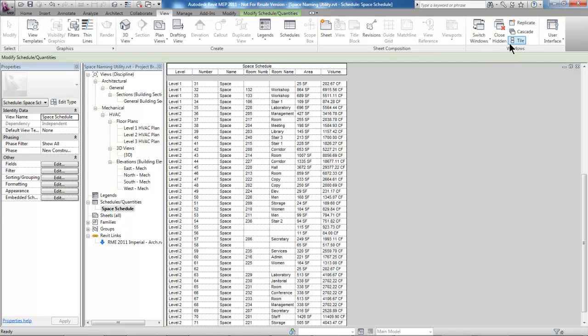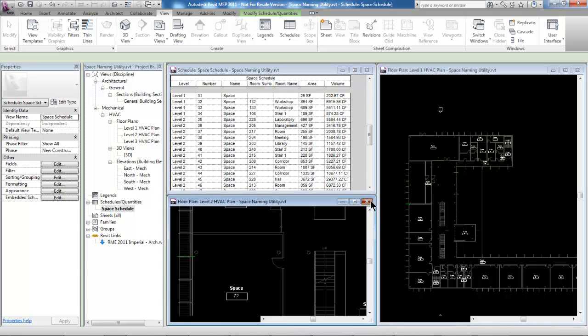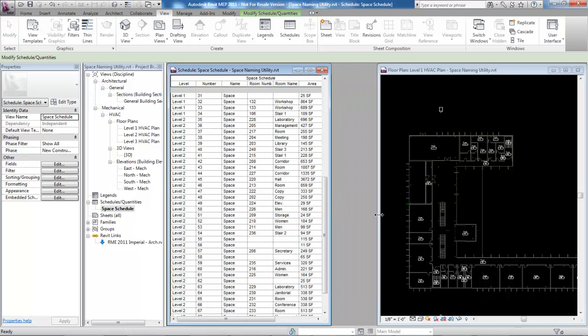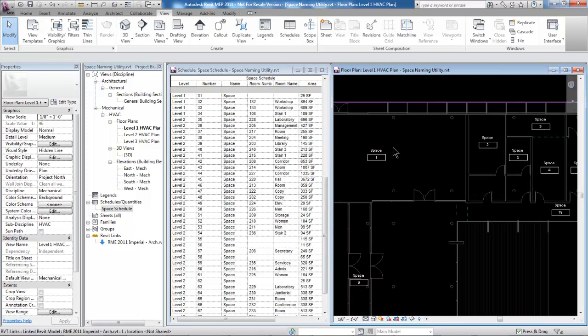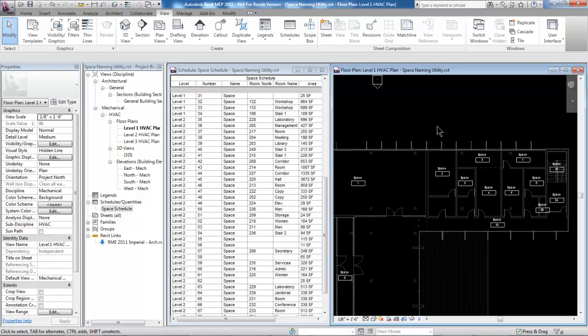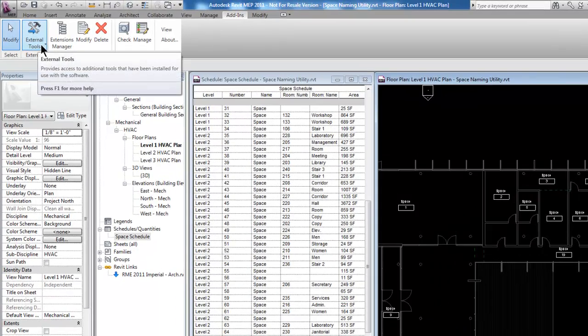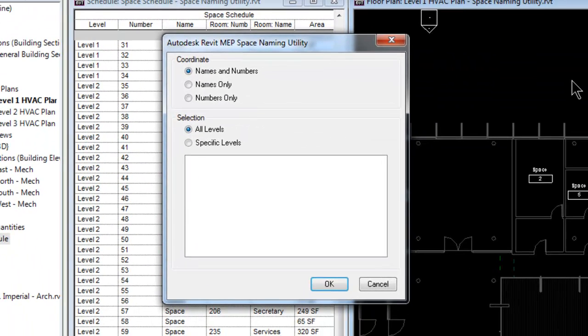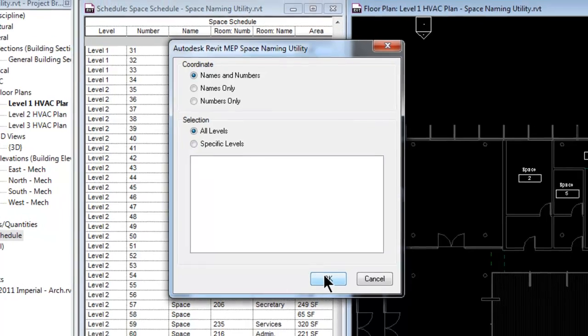So let me go ahead and tile my views — I'll tile the space schedule and the model window so you can see what's going on. Now, make sure that your plan view is active before you launch the Space Naming Utility. If I select the Space Naming Utility from the external tools drop-down, it brings up a dialog box giving me the option to choose names and numbers, names only, or numbers only. I can also be specific about which levels to process — it only recognizes levels that have spaces in them, so since I didn't place any spaces in level three, it automatically knows it can't do anything with that.